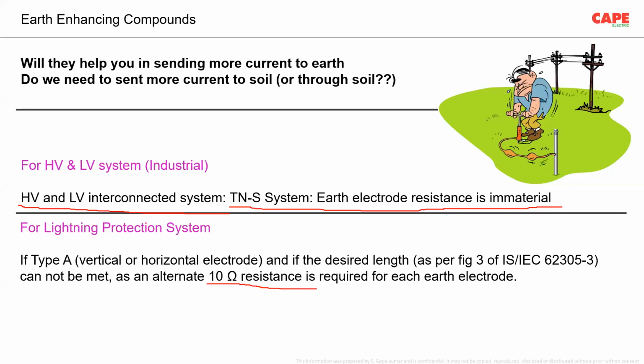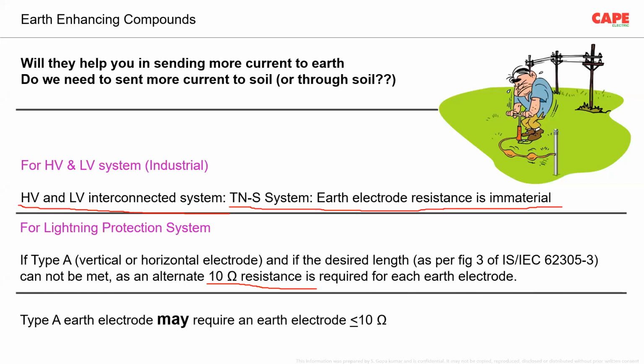So if you practically look at today's modern building where you have your own transformer, or you have a transformer very close by, the only place where you want to have a 10 ohm resistance earth electrode is for the lightning down conductor. If you go for a foundation earthing, or if you go for a ring earthing, then this value is also immaterial. Now, in a type A earthing, the earth electrode may require an earth electrode resistance less than or equal to 10 ohm. We will see this later. This is the only place where you need to have a specific value of earth electrode resistance in an industrial or in a commercial premise or in a consumer premise.